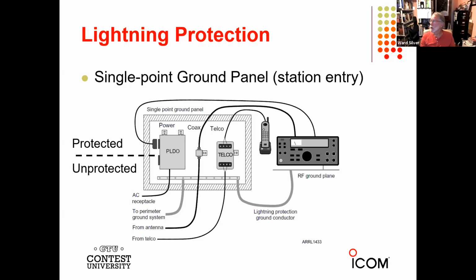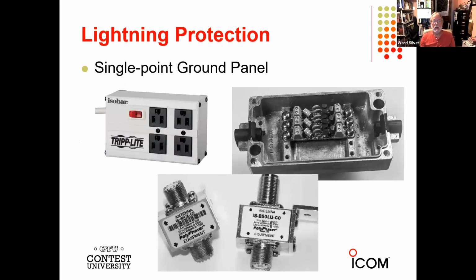or your station. So you want to make sure that you connect your RF grounds in your station, the ground plane that you use to bond everything together, to this single point ground panel. Here's some examples of what I'm talking about. A protected line duplex outlet. There's from Isobar. You can buy these in various sizes. They have transient absorbers inside. So basically you plug one of these into a branch circuit and mount it on your single point ground panel and plug everything into that.